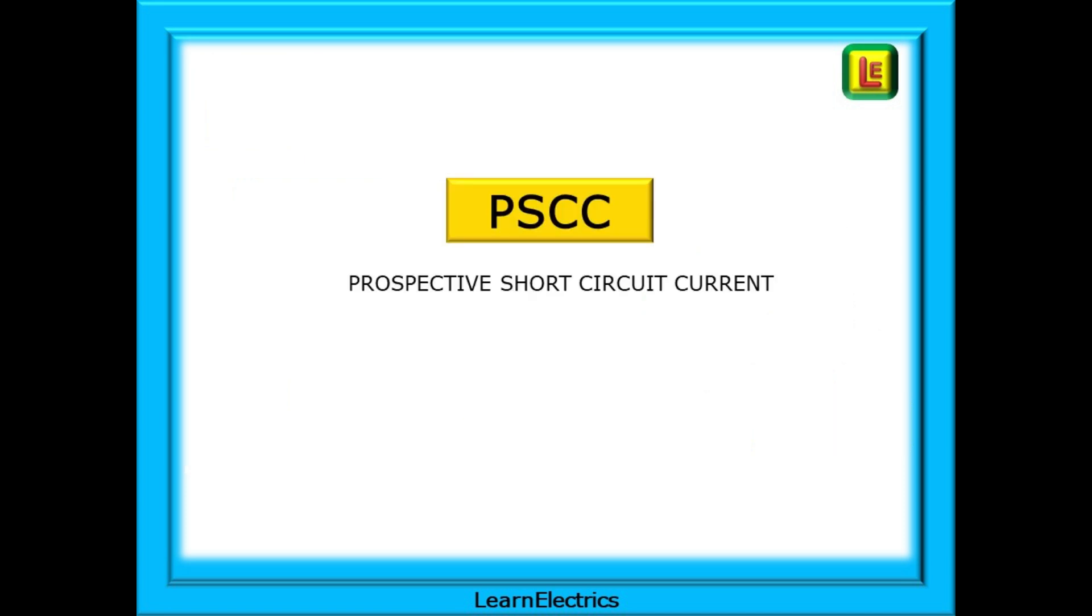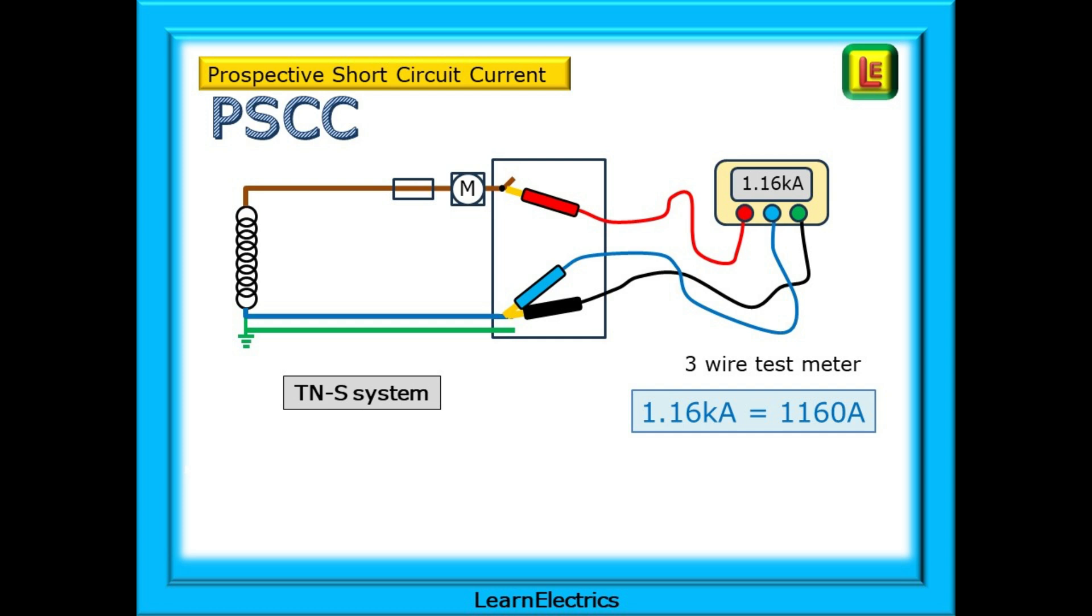We must cover the testing of PSCC as well. The full name is prospective short circuit current, and is the current that we might expect if there was a short circuit between the line and neutral anywhere in the circuit. The worst case short circuit would be at the intake position so this is where we measure PSCC. Anywhere else in the circuit will have more conductors, more resistance and so the PSCC will be slightly lower. We want the worst possible case. If the worst case is okay then all the other points of use are okay too.